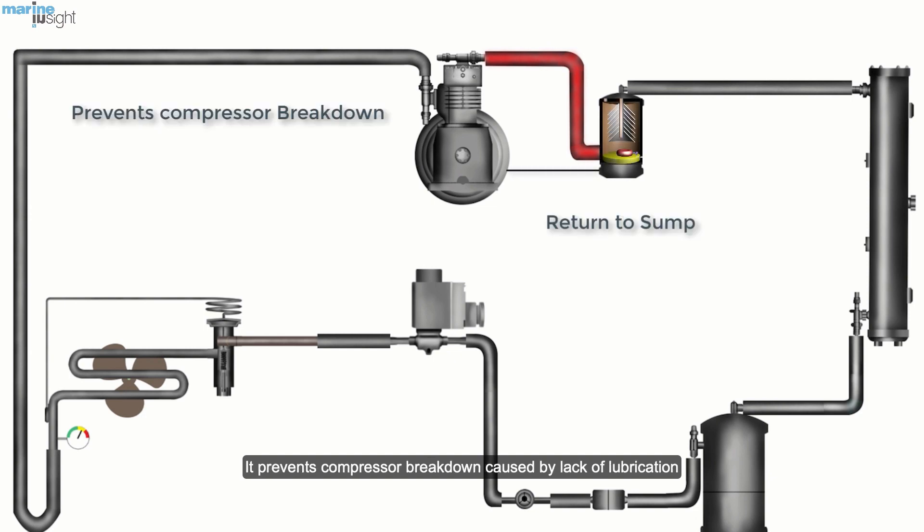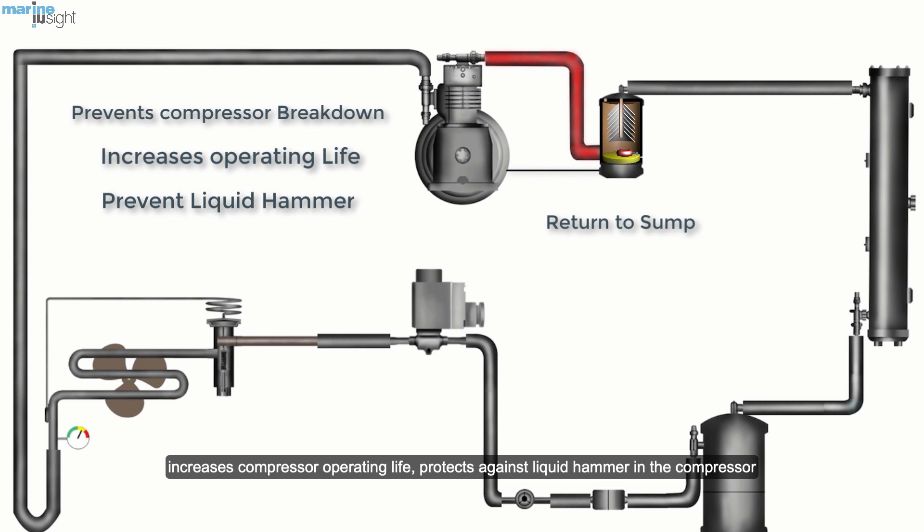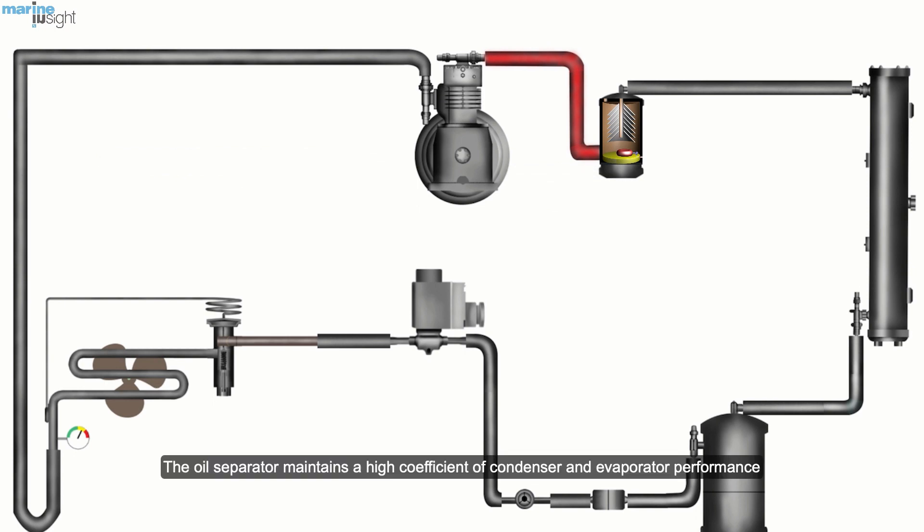It prevents compressor breakdown caused by lack of lubrication, increases compressor operating life, and protects against liquid hammer in the compressor. The oil separator maintains a high coefficient of condenser and evaporator performance by almost completely removing oil deposits from their exchange surfaces.